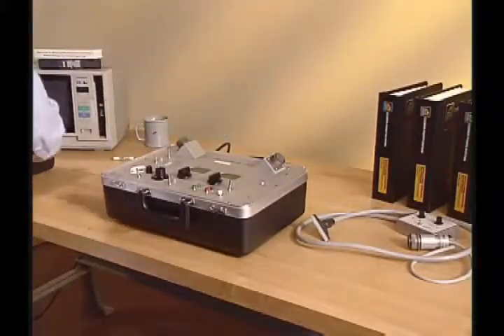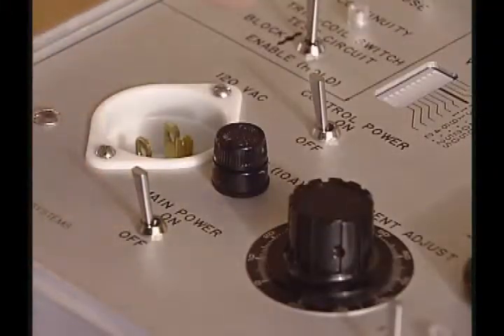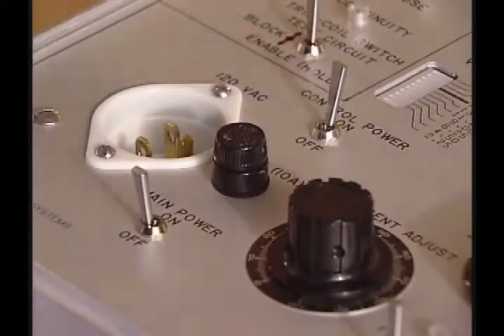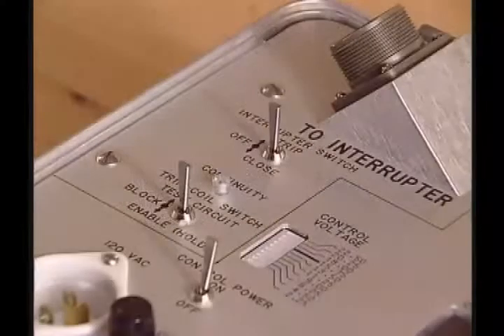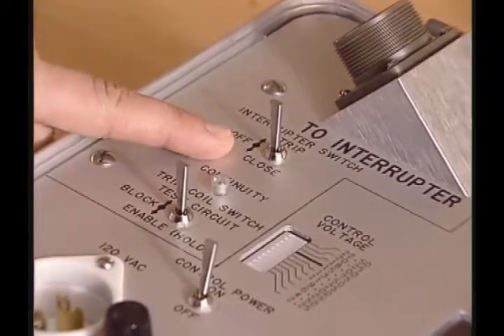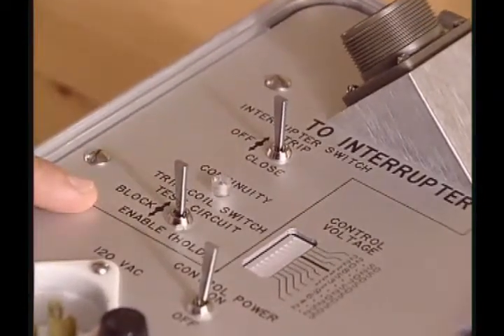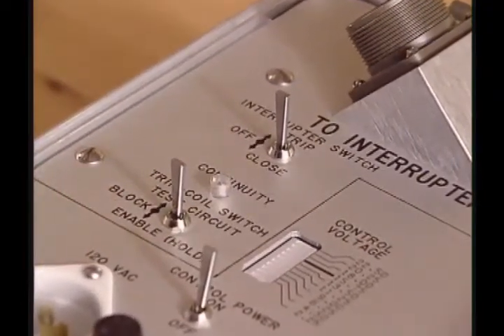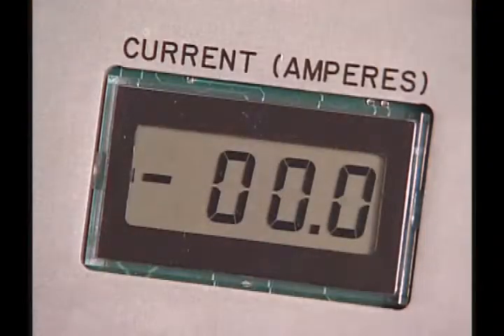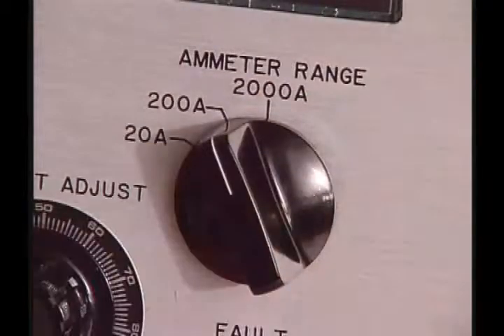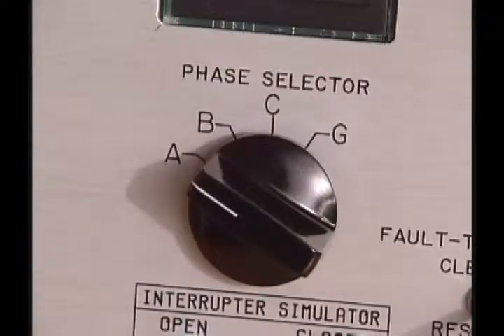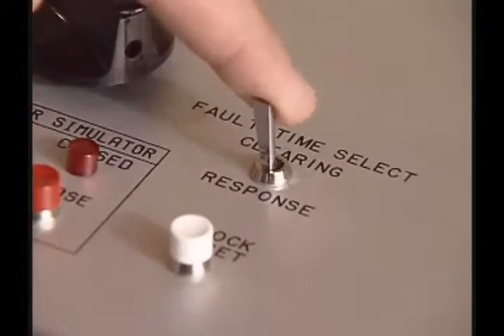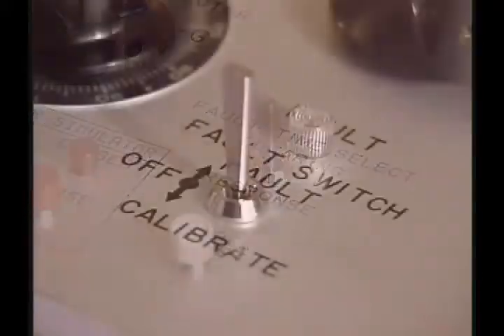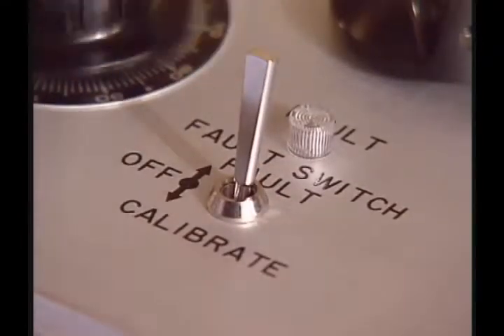To prepare the tester, make sure the main power switch is off and the control power switch is on. Also make sure that the trip switches in the 2 interrupter panel section are in the off and block position. Adjust the current to 0, the ammeter range to 200 amps, the phase selector to A, the fault time select switch to response, and the fault switch to the fault position.